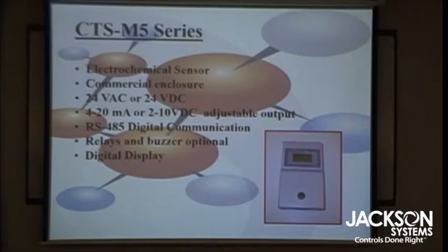This comes standard with a display, also an adjustable 4 to 20, RS-485 or daisy chain communication. The only options are really relays and buzzers. So if you want to use it as a standalone and also have an audible alarm, you can have it. Very rugged unit. It's been around a long time. I think ACI has probably sold in the past 5 years probably about 20,000 of these things.